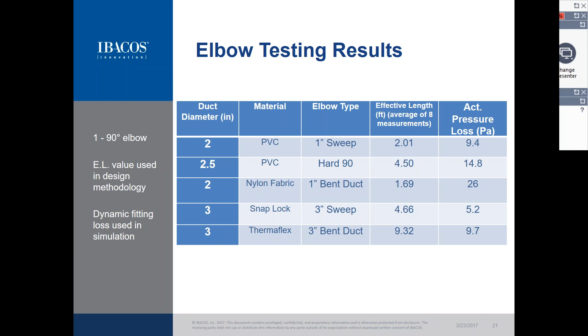We conducted a very basic applicability study where we took some of this data along with the prototype design tool and applied designs to floor plans of houses across multiple climate zones and enclosure types. We had basic assumptions about the duct system layout, assuming about 0.35 inches of water of available static pressure. We wanted a simple check to see what the limiting factor or applicability might be for this system in homes across the U.S.